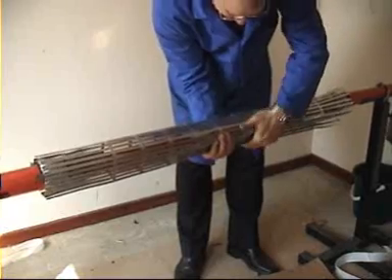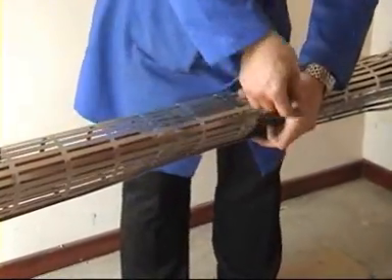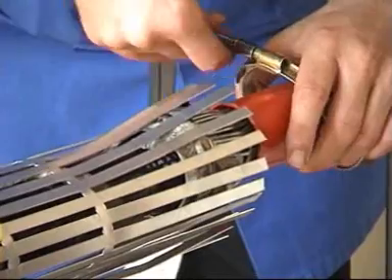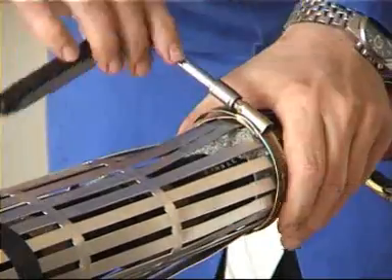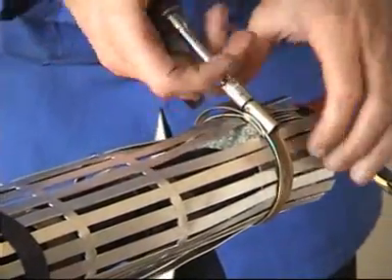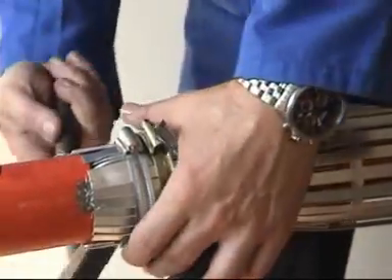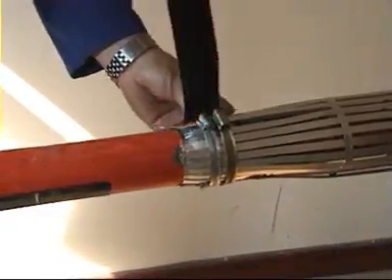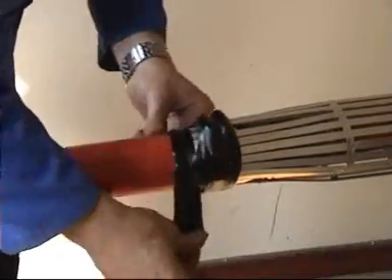Now wrap the armour casing around the joint cap holding it together with PVC tape and using the armour clamps clamp down the fingers upon the support rings. Tap down any sharp points and apply black mastic tape over the clamp buckles and over the sharp finger points.